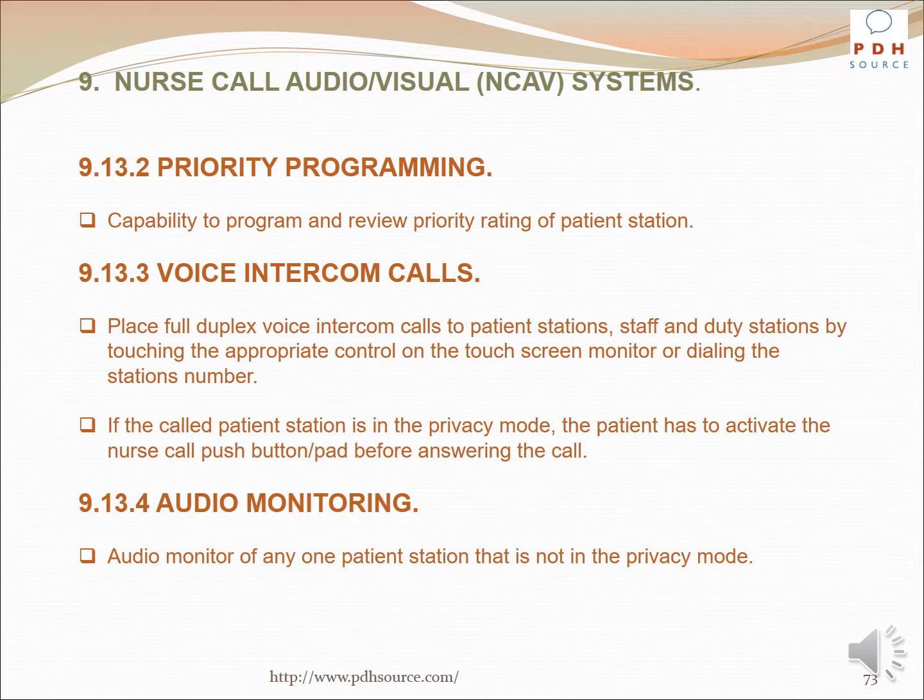Place full duplex voice intercom calls to patient stations, staff and duty stations by touching the appropriate control on the touchscreen monitor or dialing the station's number. If the called patient station is in the privacy mode, the patient has to activate the nurse call push button pad before answering the call. Audio monitoring of any one station that is not in the privacy mode shall be provided.